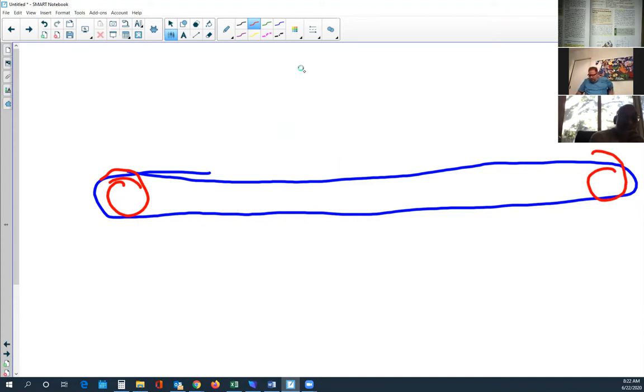But let's say we wanted to line up a start mark with a hopper. And here's the start mark. We don't want to push start because this thing is just going to take off. So we'll jog or we'll inch. So we just bump it. We bump the start button, but we don't allow the maintain or holding contacts to energize or pull in. So we bump, bump, bump, bump. There, it's lined up. That's where we wanted it. So that's where we got the start position. Now we can start the process and push start and everything's going to work out just fine. That's what they mean by inching or jogging. It's just giving a little bit of electricity to the motor just to move that conveyor belt a little bit, just inching.